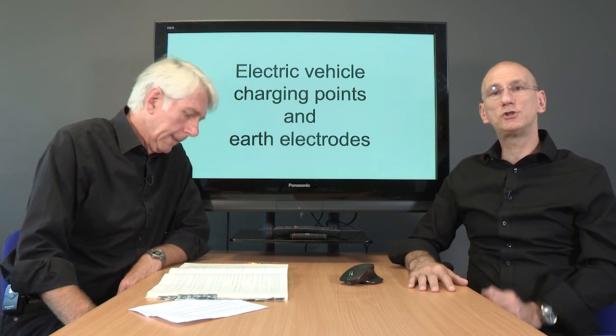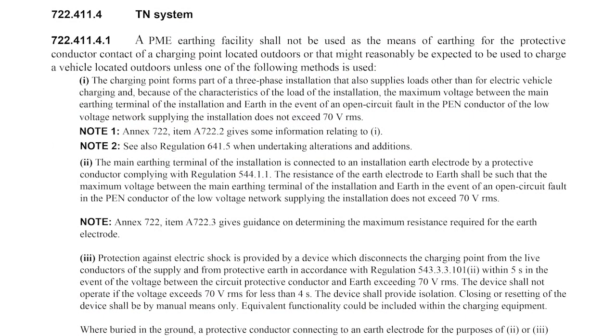Okay, so we're in section 722, 722.411.4.1. And we went through the four options, three numbered options and then a fourth in the next reg, as to how you can deal with the earthing on vehicle charging points. Yes, predominantly we're talking about the issue of PME. And what does it state there? A PME earthing facility shall not be used as a means of earthing for the protective conductor contact of a charging point located outdoors, or that might reasonably be expected to be used to charge a vehicle located outdoors, unless one of the following methods is used.